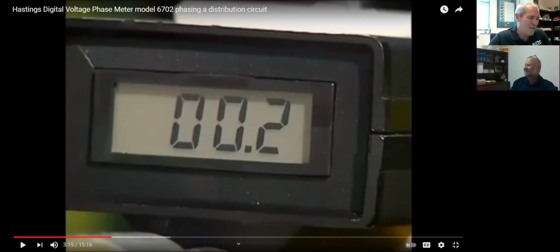Yeah, you got line impedance on this other line that's showing a little differential in the voltages, okay? And that's why you're getting a 0.2 volt difference of potential. Is it still the same phase? Yes, but line impedance is giving you a little bit of a difference in voltage reading.